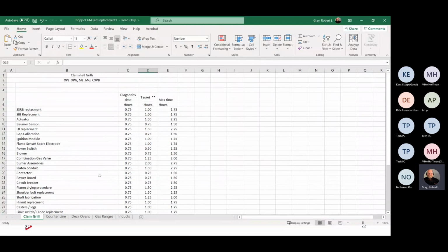This is the standard repair time for clamshell grills. So a solid state relay board, for example. You have 45 minutes to diagnose the problem. Well, I'm going to get you into it where you can diagnose the problem within 15, 20 minutes or less. Then the target repair time, once you figure out that it needs to be replaced, is 1 hour. So your max time is 1 hour, 45 minutes. Anything over that, the warranty system that your point of contact or warranty person is entering it in, if it's over, it's going to be flagged, and then the system will send it off to a warranty specialist for review.